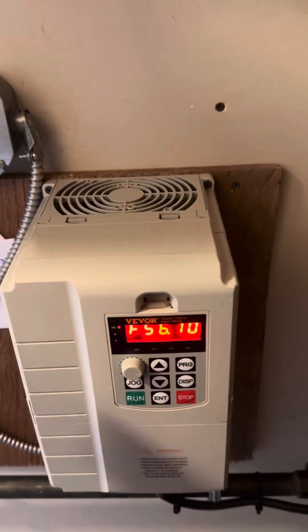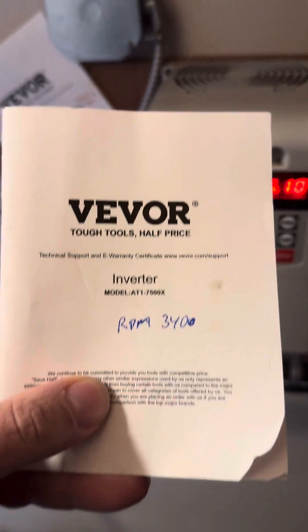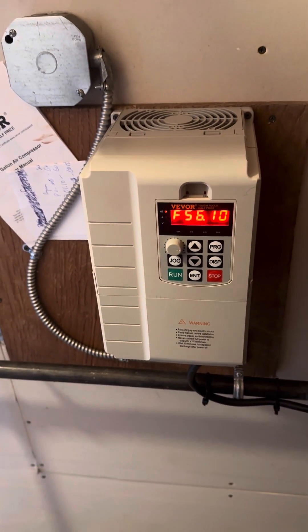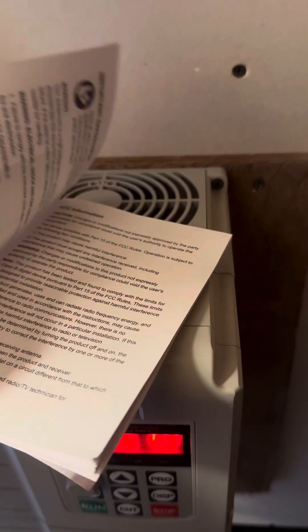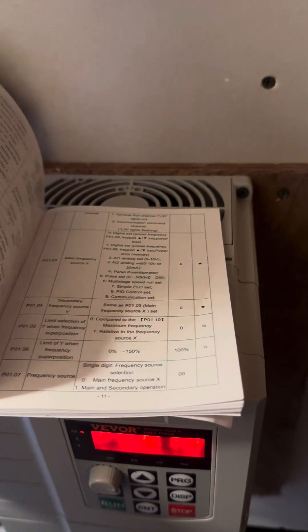There are pretty basic settings to get this up and running. This is the VEVOR AT1-7500X, 10 horsepower — this compressor is 6.5 horsepower, so do not undersize your VFD or it won't last. You need to oversize it slightly and then program it for the frequency. If you're not familiar with electrical, I would not recommend doing the wiring yourself — hire a certified electrician to do the wiring, and they can also do the programming if you show them this video.